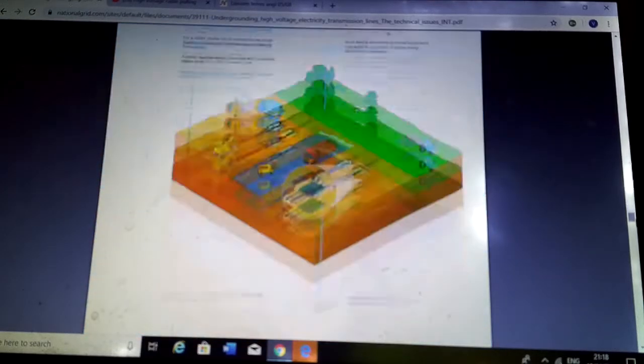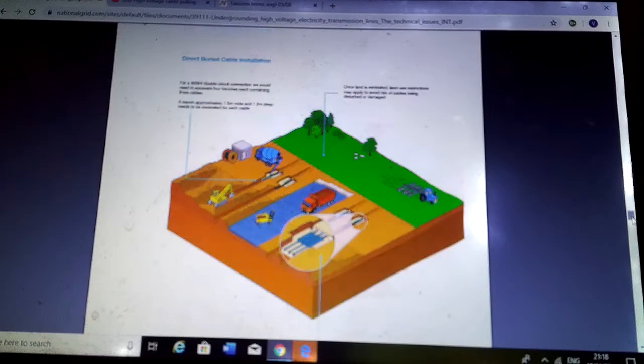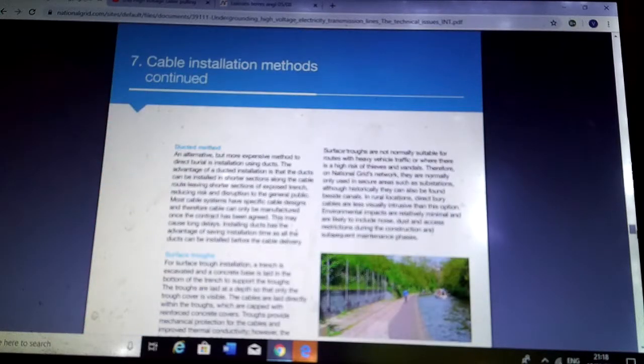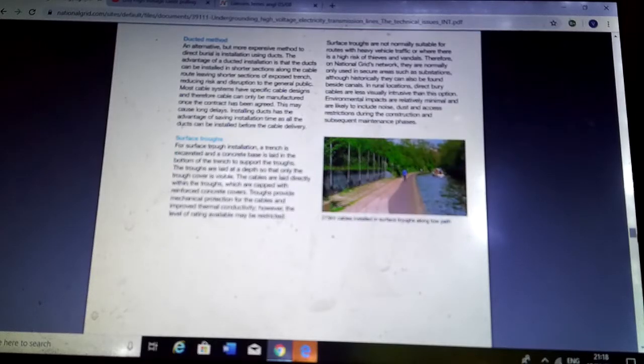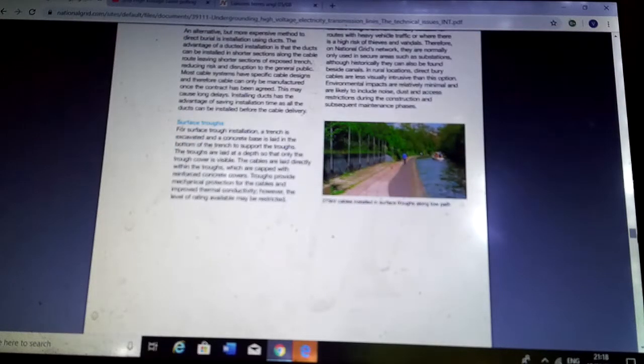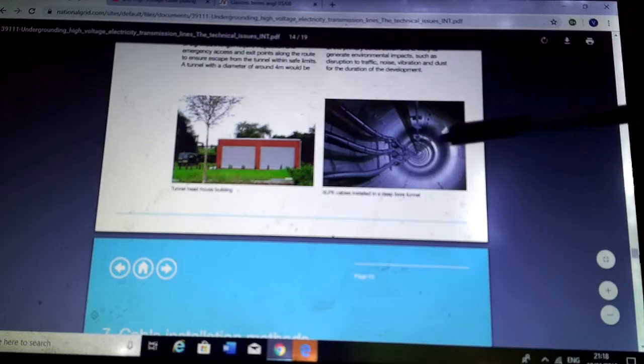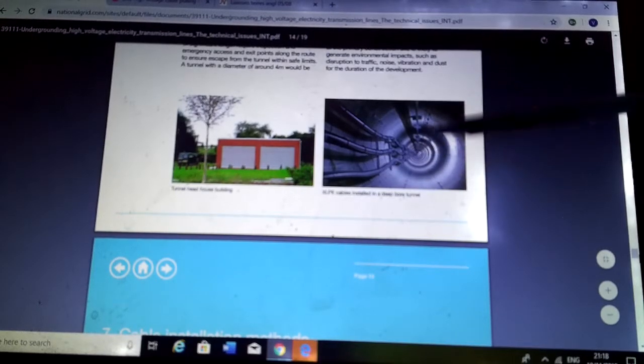You can read that yourself because I have to be very conscious of time. And there's a direct buried cable installation in a rural area there. It looks to be a very dry area, and there's a good diagram there showing you how it's done. There's a 400 kV double circuit, and that's our line here. So well worth reading that, folks, if you can get at it. Cable installation methods continued. There's one along a canal, cables installed in surface troughs along a canal, and this is the one I mentioned where you have the big tube. It's like a train tube, and you see the cables along here, and a person can walk through that. Well, that's state of the art, and then there's a building every so often to get into it. That wouldn't really, I don't think, be feasible for the North-South Interconnector due to cost.